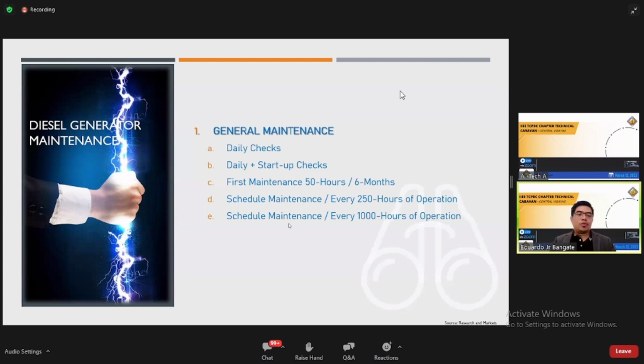Now let's go to diesel generator maintenance. What are the general maintenance we put into our diesel generators? We have the daily checks, the daily plus startup checks. We have the first maintenance at 50 hours or 6 months, scheduled maintenance every 250 hours of operation, and scheduled maintenance every 1,000 hours of operation.